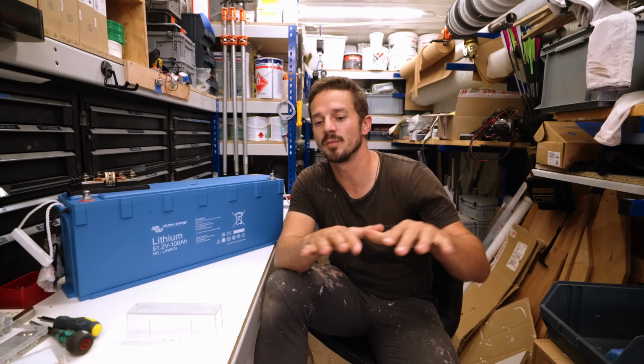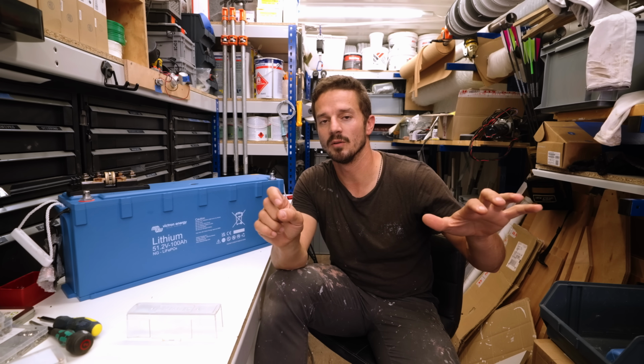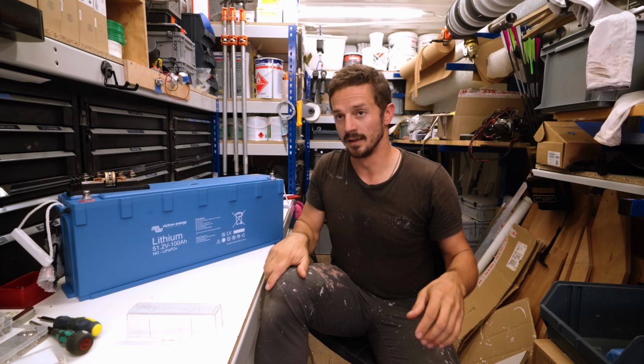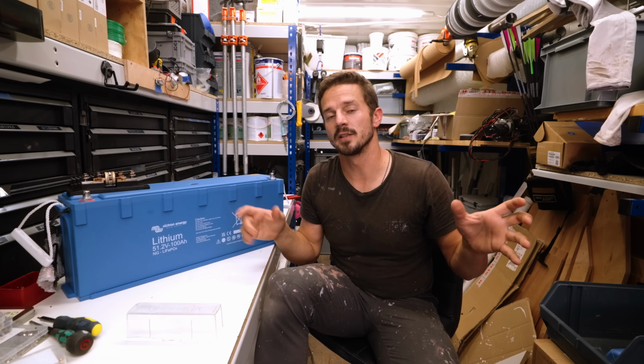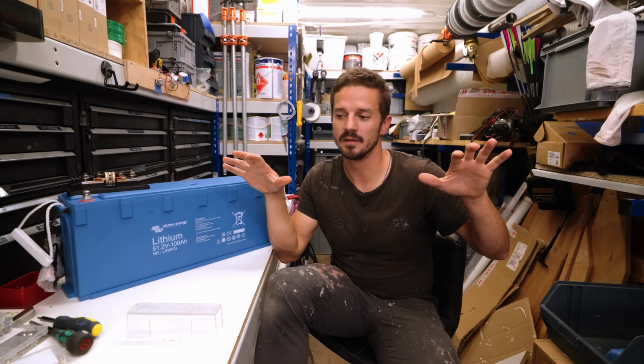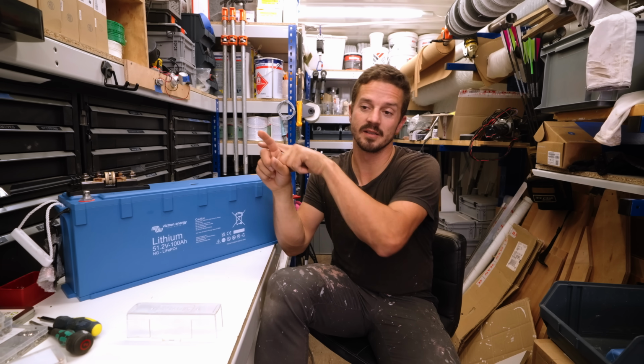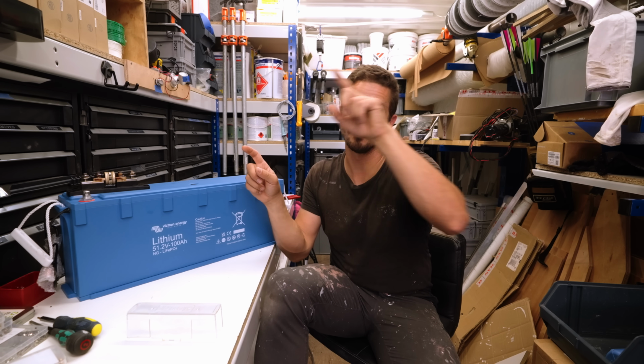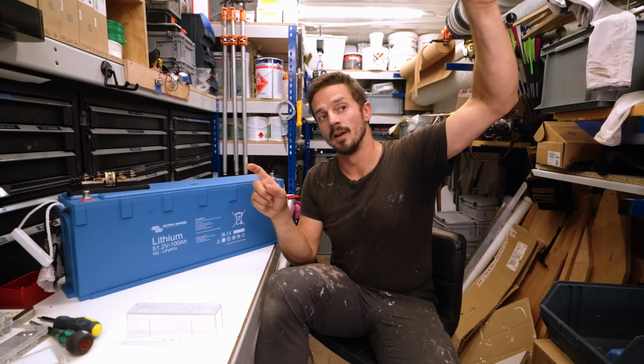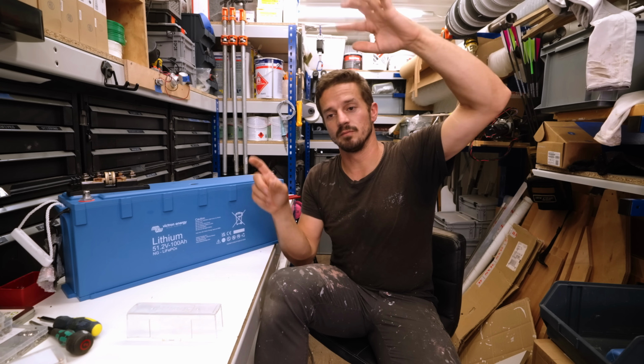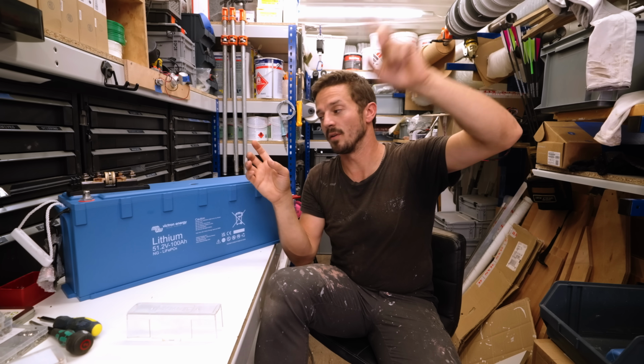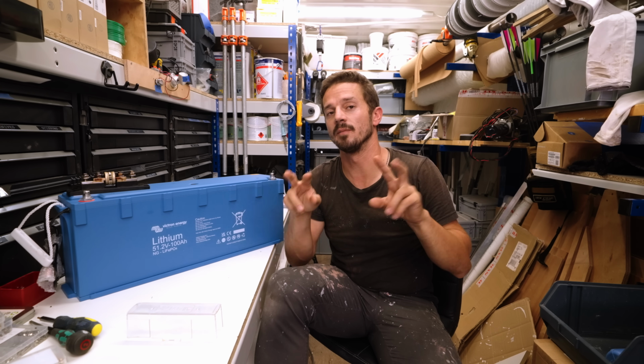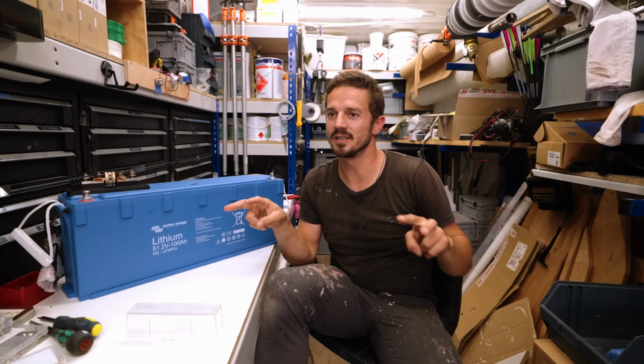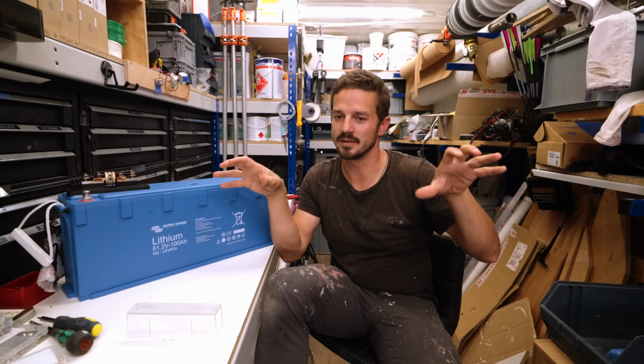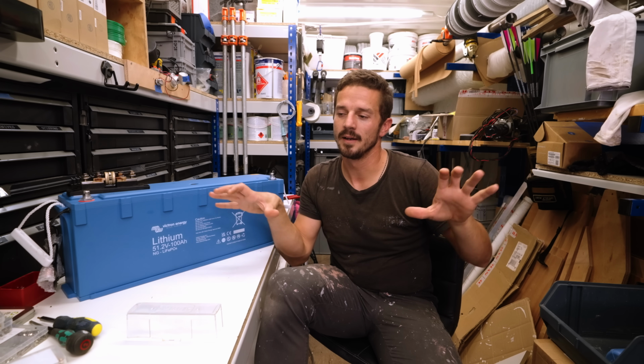The other design requirement is that since we have 2 identical matching battery banks running off the single bus bar, the battery banks need to be symmetrical, so the loop resistance - from the positive through the fuse, through the bus bar, up to the Lynx Distributor, out to whatever it needs to go to, and back on the negative - is the same for both battery banks. This ensures both banks get the same level of charging.